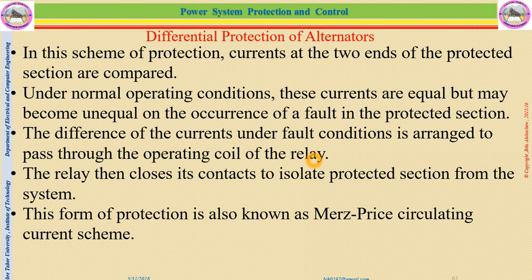The other thing is differential protection of the alternator. Since stator winding failure involves several types of faults, some protection mechanism is required. One of the protection mechanisms for the generator stator winding is differential protection. So what does differential protection of the alternator mean? In this system of protection, the currents at the two ends of the winding are compared, before and after generation. So at the ground side and at the load side, we compare the two currents. If they are the same, that is a normal condition. If there is a difference between the ground side and the load side, there is a problem.